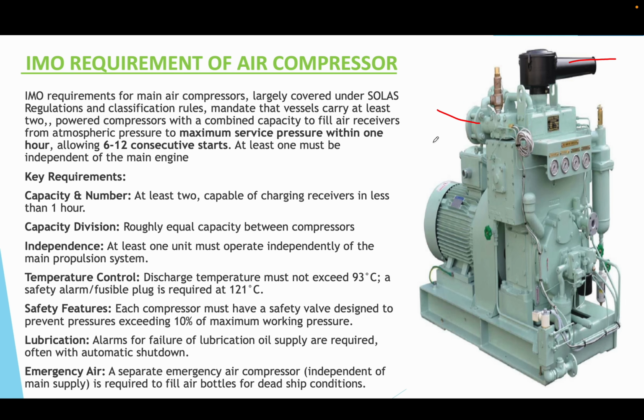The air bottle has a fusible plug. That temperature should not exceed 120 degrees Celsius. The second thing they say is that there should be a safety valve provided in each air bottle which should lift when the pressure reaches 10% above the maximum working pressure, and also in the compressor there is a safety valve provided which should lift in case the pressure abnormally rises above 10% of the maximum working pressure.